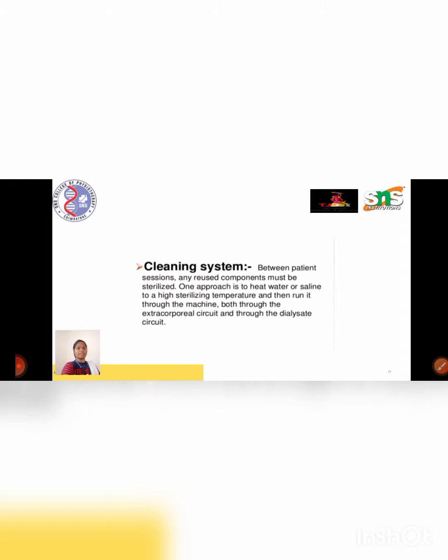Cleaning system. Between patient sessions, any reused component must be sterilized. One approach is to heat water or saline to a high sterilizing temperature and then run it through the machine, both through the extracorporeal circuit and through the dialysate circuit.